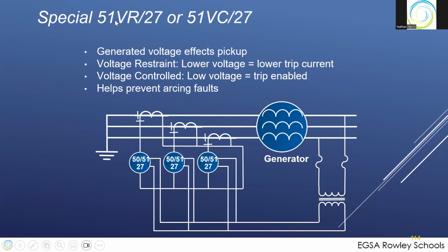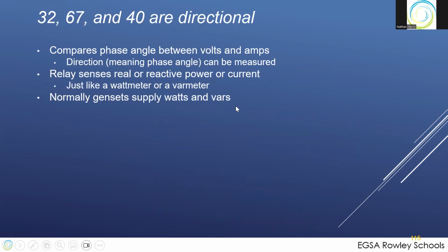In that case, we use a voltage controlled or voltage restrained relay. That is, as the impedance increases real high, the voltage tends to drop. As the voltage drops, you want to trip faster. So this is detecting both current and voltage, and at a high level of current, often with a suppressed output voltage due to this fault pulling the voltage down, it'll actually trip at a lower value. Prevent those kinds of arcing faults we saw at first there.